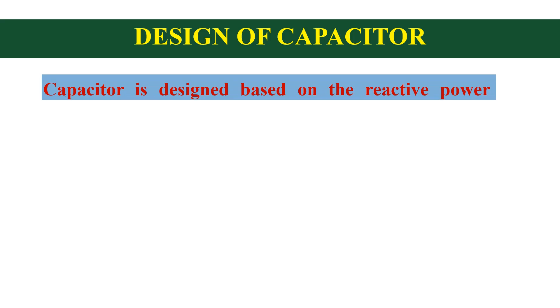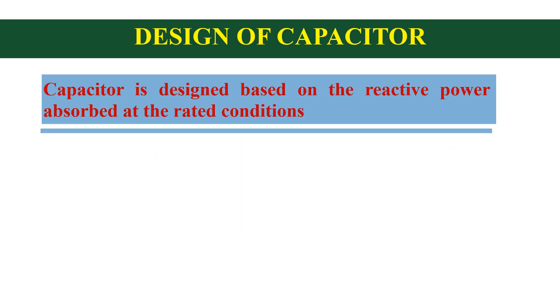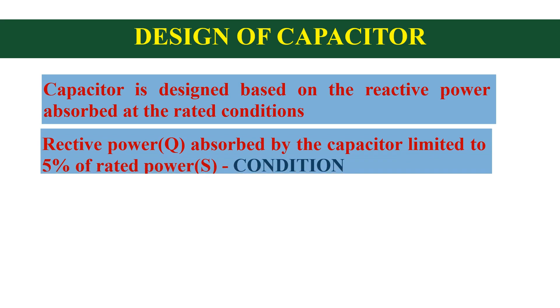Now we will look at the capacitor design. Capacitor is designed based on the amount of reactive power it absorbed. It can take reactive power from the source or the grid. As a thumb rule, reactive power absorbed by the capacitor is limited to 5% of the rated power.